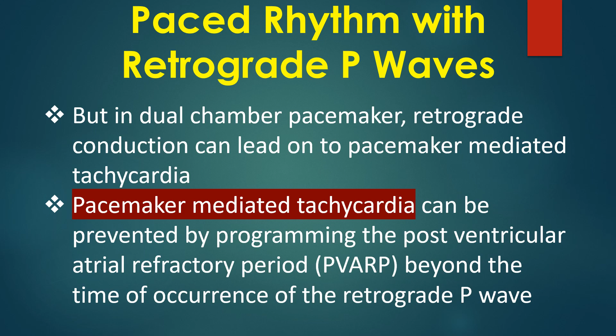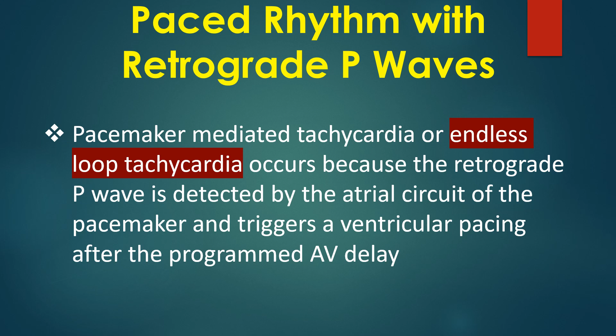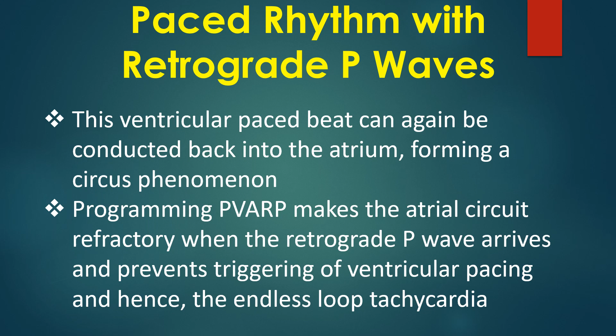Pacemaker mediated tachycardia or endless loop tachycardia occurs because the retrograde P wave is detected by the atrial circuit of the pacemaker and triggers a ventricular pacing after the programmed AV delay. This ventricular pace beat can again be conducted back into the atrium, forming a circus phenomenon. Programming PVARP makes the atrial circuit refractory when the retrograde P wave arrives and prevents triggering of ventricular pacing and hence the endless loop tachycardia.